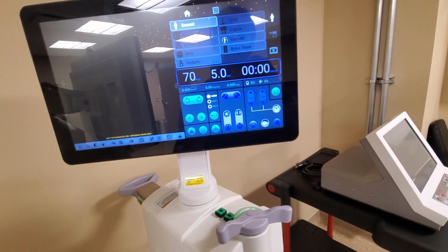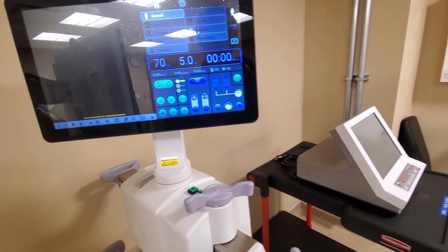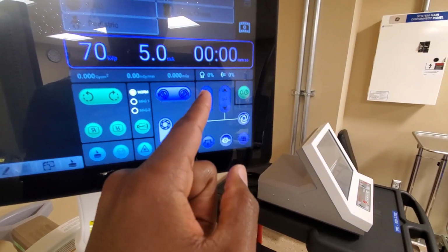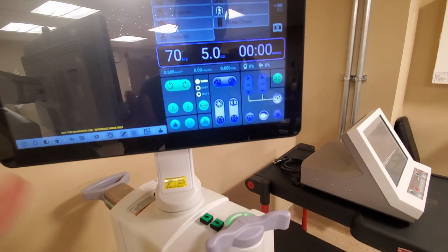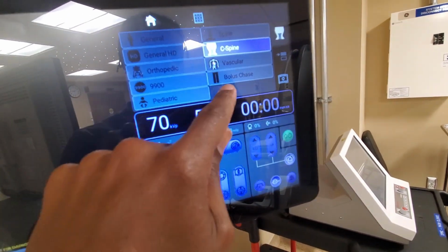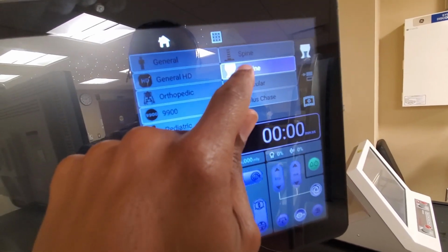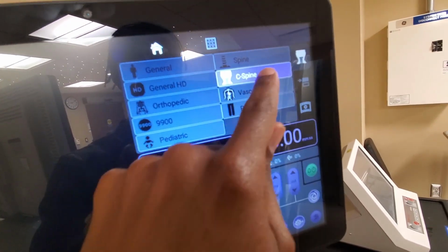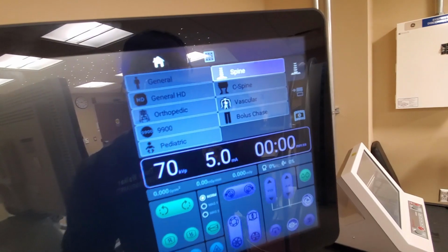With time, I've learned, I've been doing IR for 6 months for a clinic, and you never want to adjust the mA and kV, ever, never. Patient's thin, the patient's thick, it doesn't matter. You want to just change the settings this way. So if you're doing the neck and the patient's thick or has broad shoulders, just use the spine histogram to penetrate through the patient's shoulders.